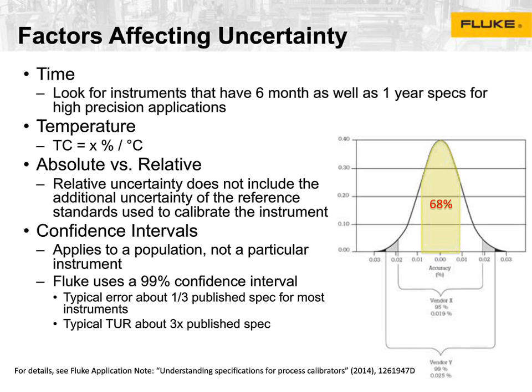And so the absolute uncertainty, which some manufacturers quote, will actually give you the error of the equipment used to calibrate all the way through the chain. And that can be very, very useful because you know that the equipment was probably calibrated by the highest quality gauges and other equipment to get it the most accurate.